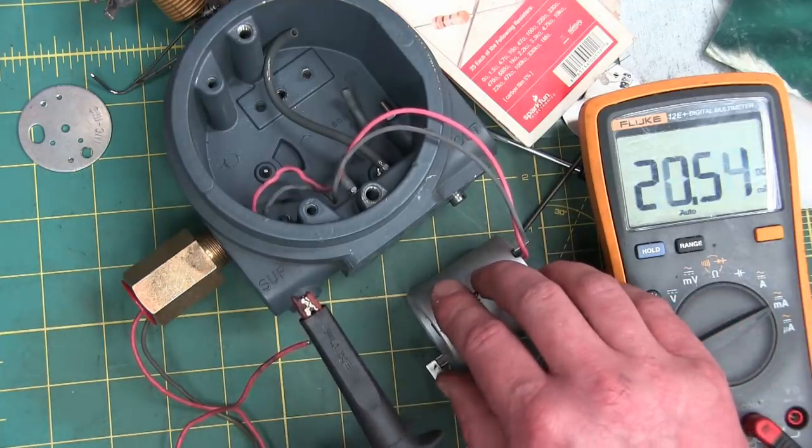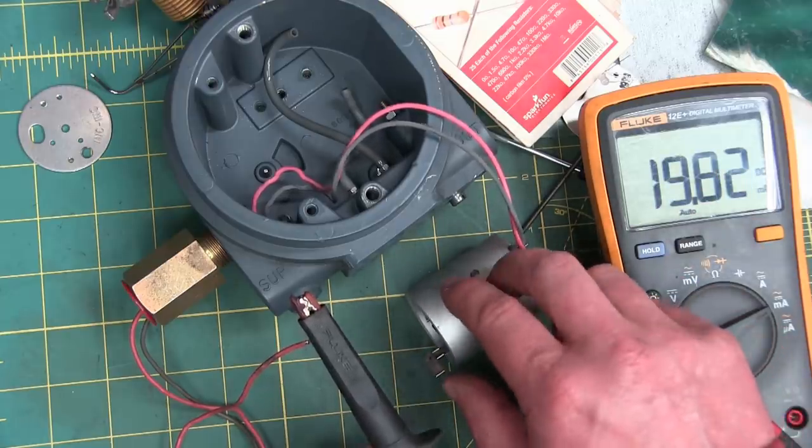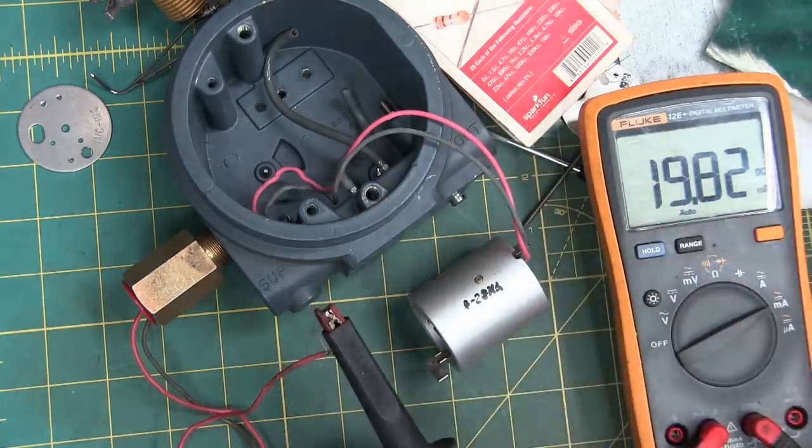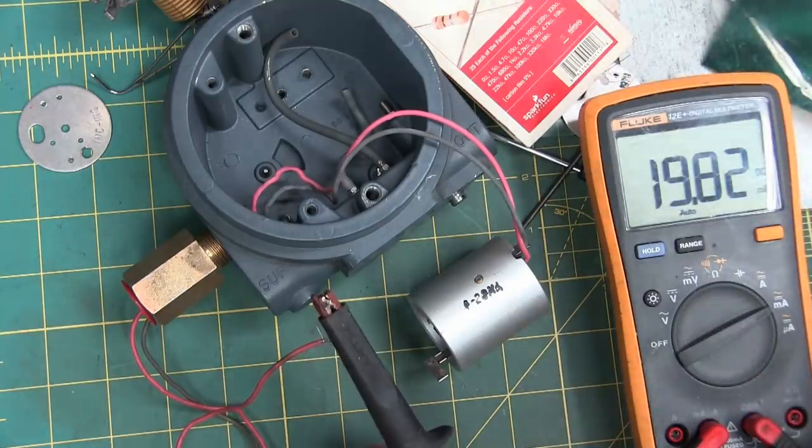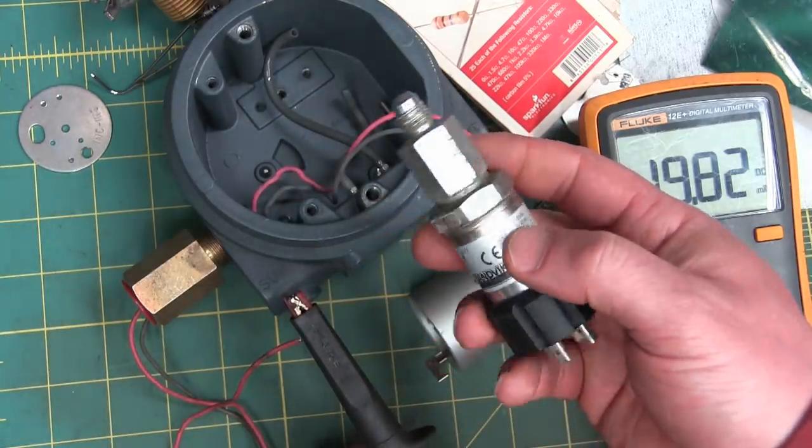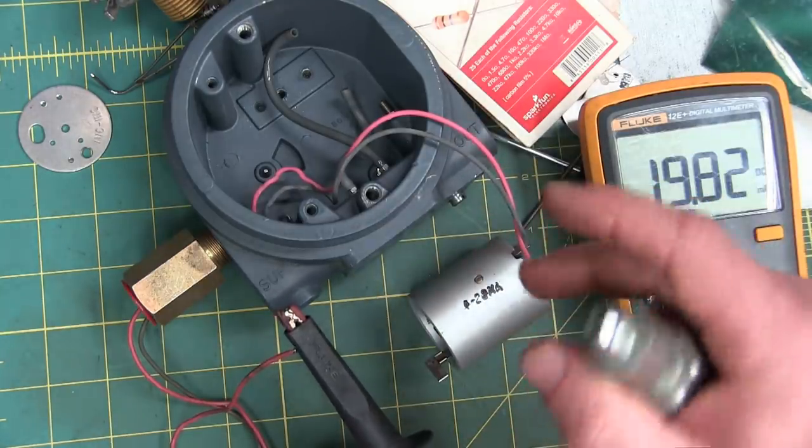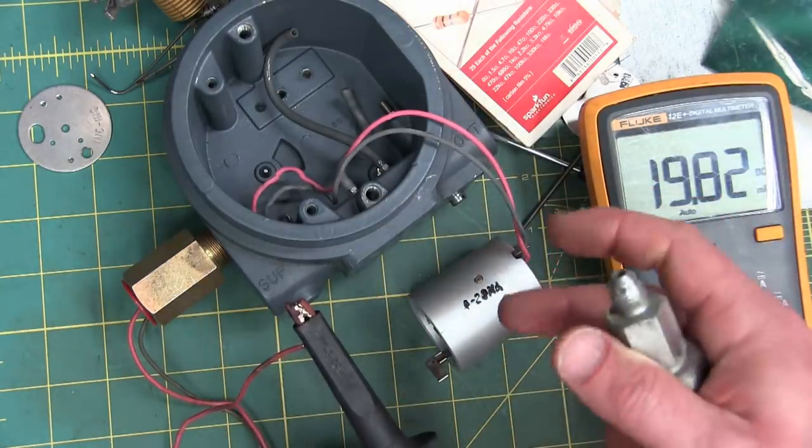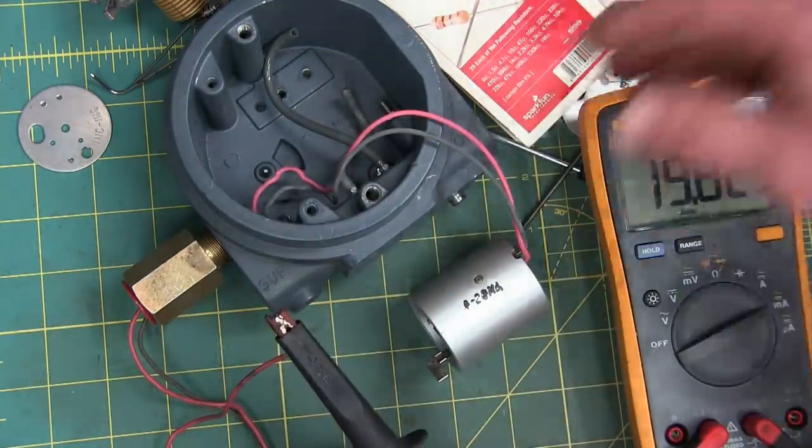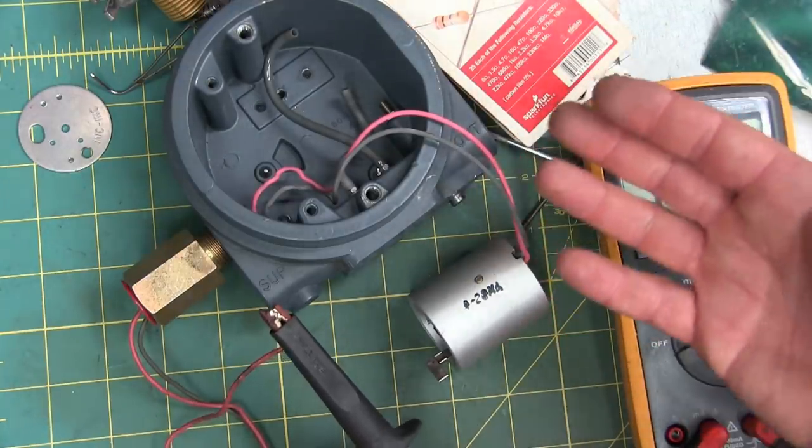Still not working. So either I am... Well, I'm not well versed in these analog instruments that don't have any electronicals in them. Normally, you feed them the voltage. Like these guys. You feed them the voltage. Any voltage. And they output 4 to 20 milliamps. This, I think, is a little more finicky. You gotta get the right voltage going through. Or you gotta tweak it a little bit. So in that case, other than being super interesting because it's electromechanical, maybe a bit more of a pain in the arse.